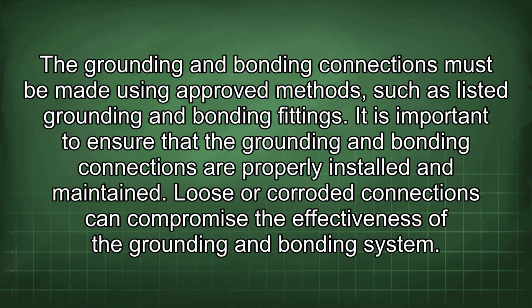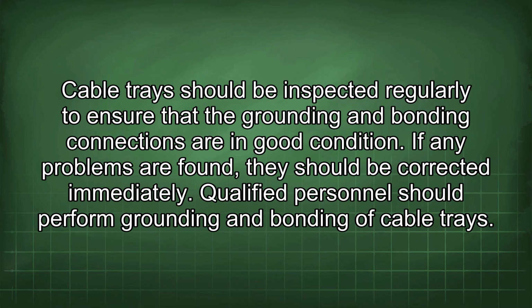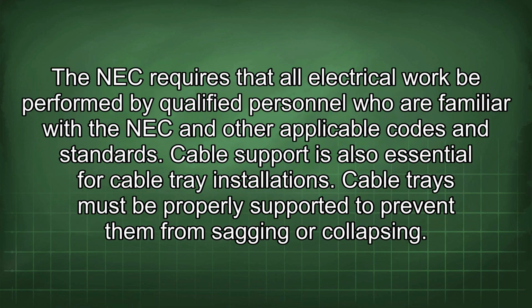It is important to ensure that the grounding and bonding connections are properly installed and maintained. Loose or corroded connections can compromise the effectiveness of the grounding and bonding system. Cable trays should be inspected regularly to ensure that the grounding and bonding connections are in good condition. If any problems are found, they should be corrected immediately. Qualified personnel should perform grounding and bonding of cable trays. The NEC requires that all electrical work be performed by qualified personnel who are familiar with the NEC and other applicable codes and standards. Cable support is also essential for cable tray installations.